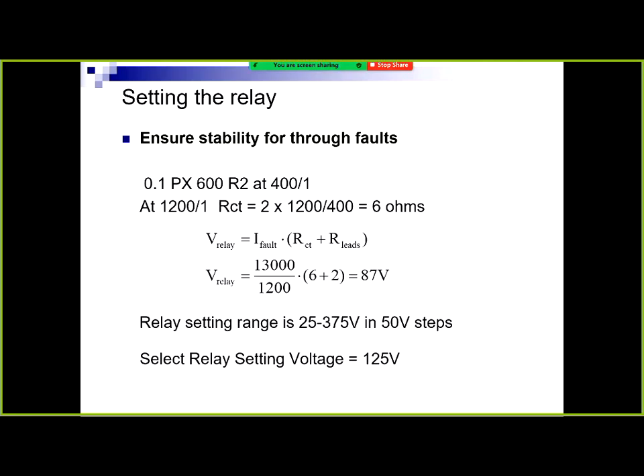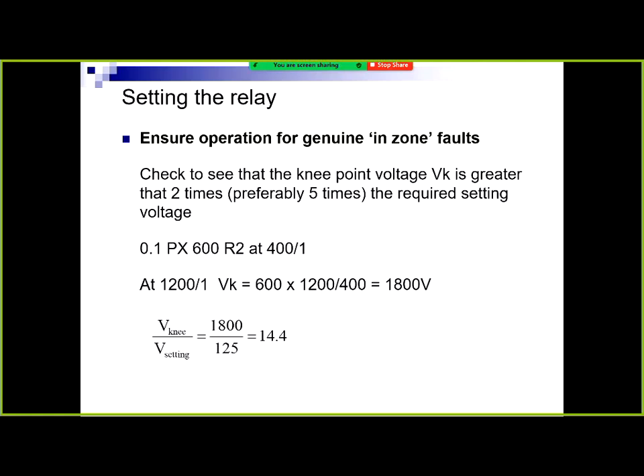So if we have an external fault, the CT saturates, will still be stable. If you get an internal fault, you're going to get a whole lot of volts in that internal circuit and your relay is going to trip because it's above 125 volts. So a lot of current, high impedance, it's a high impedance thing. High impedance, high current equals high volts.